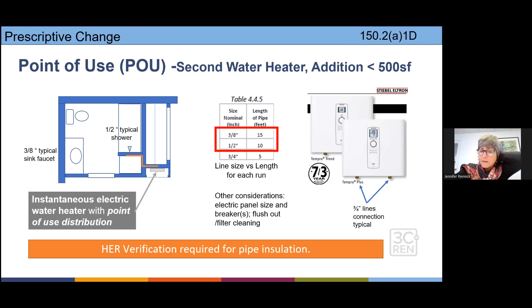And then these are additive. So let's say we had only a couple of feet of the 1/2 inch. To make it easy, you could say, well, I have 5 feet of 1/2 inch, I could have 7.5 feet of 3/8 inch, but you're allowed to add those together proportionately to meet these requirements. But really what you want to do is get down to the smaller pipe size right away and do parallel piping.